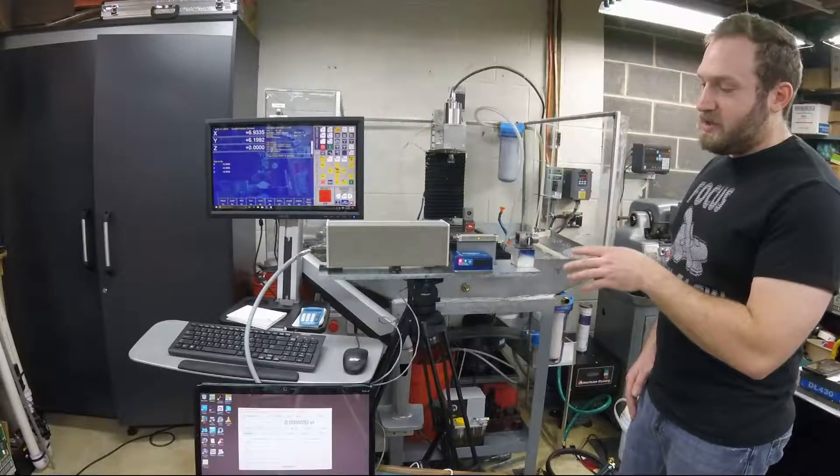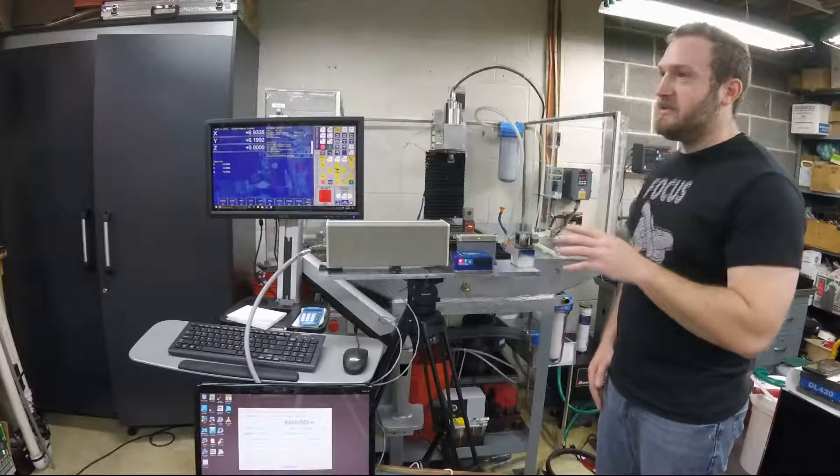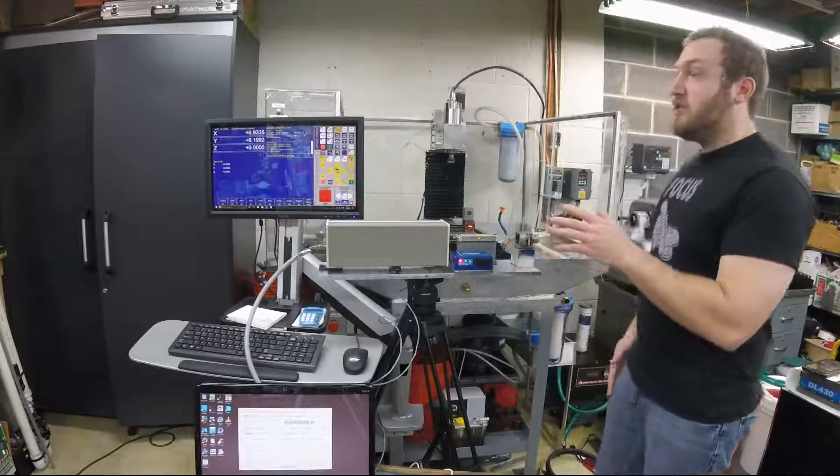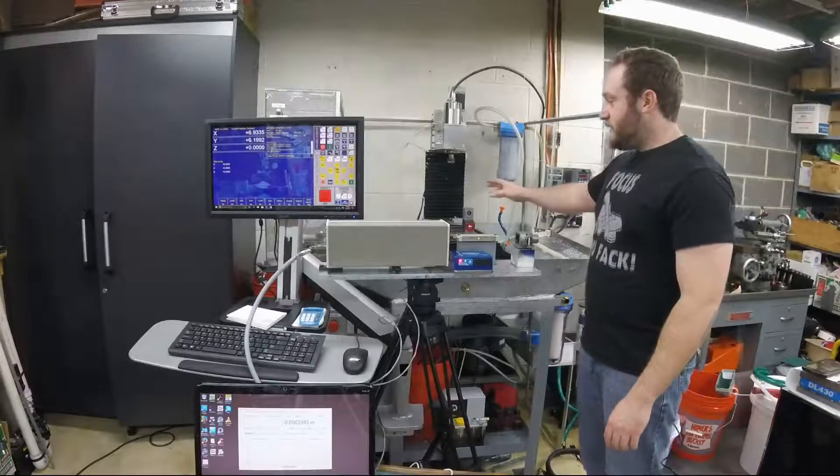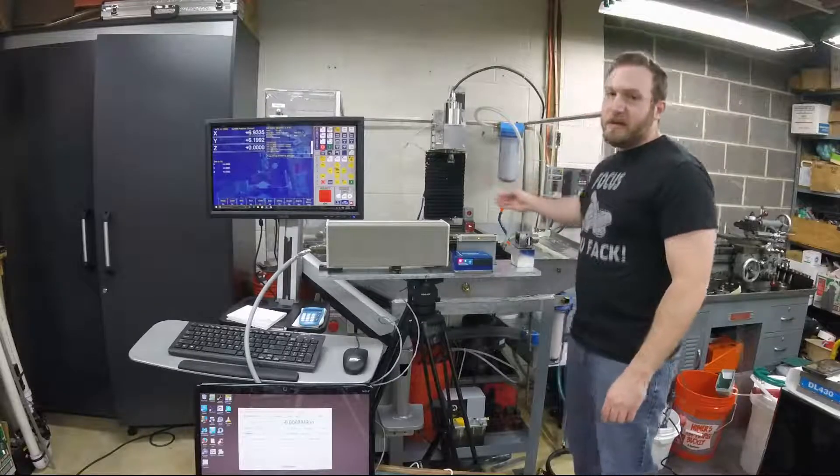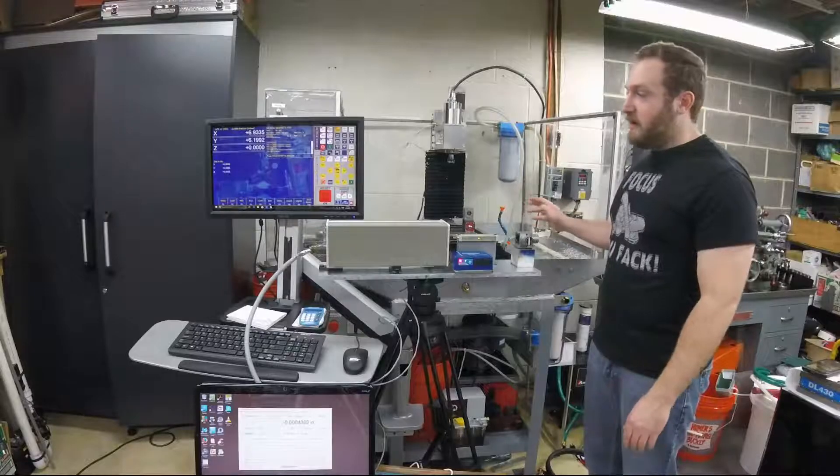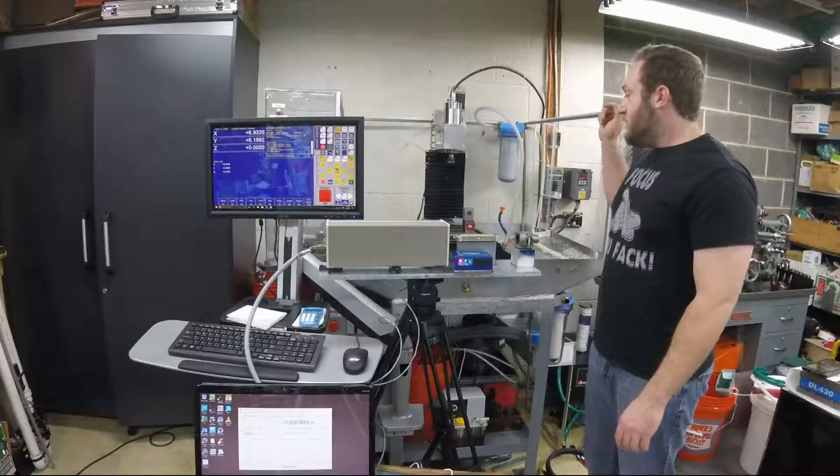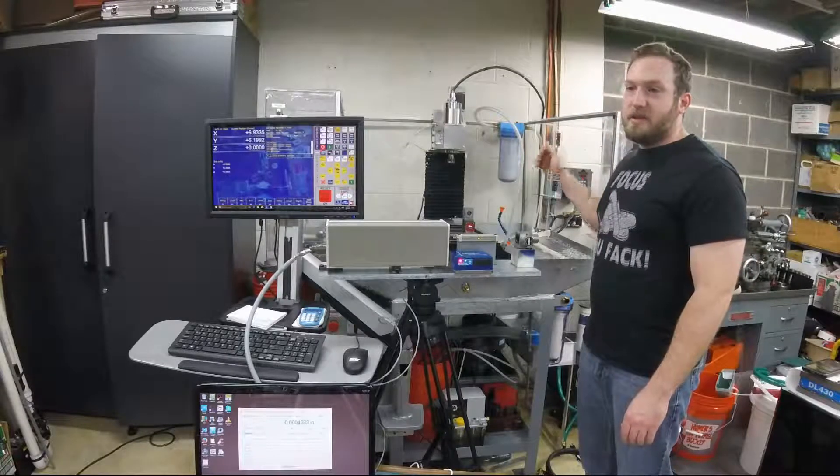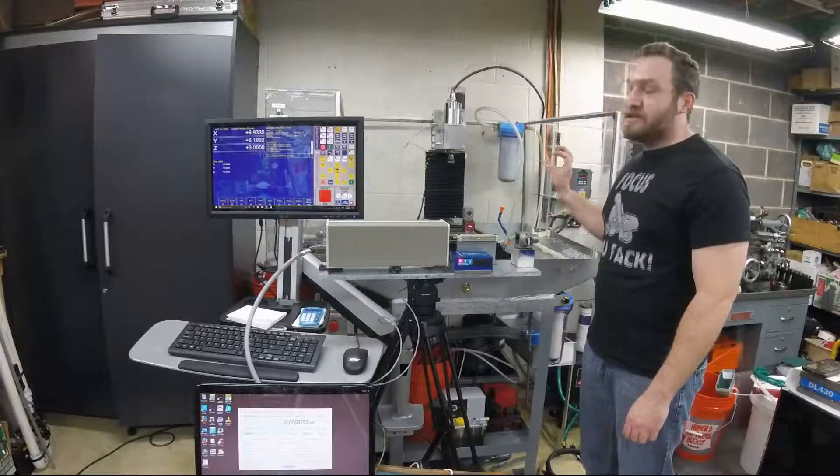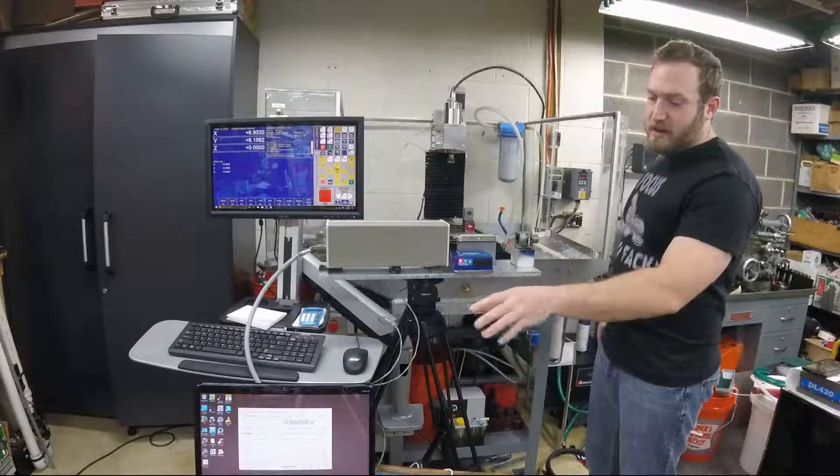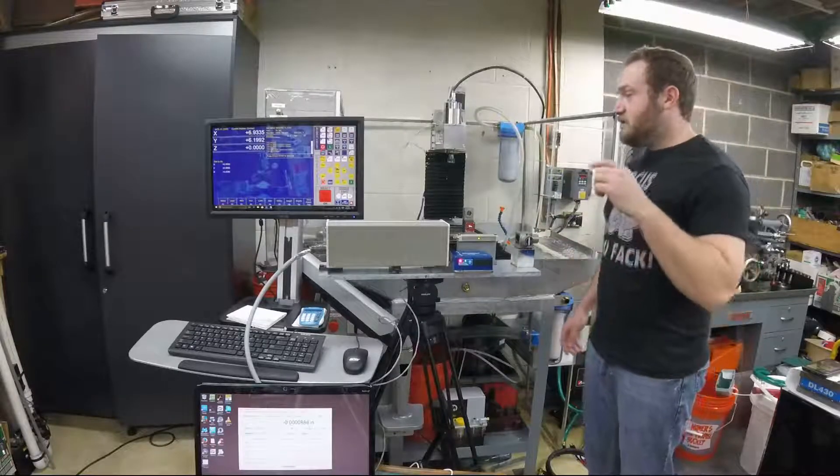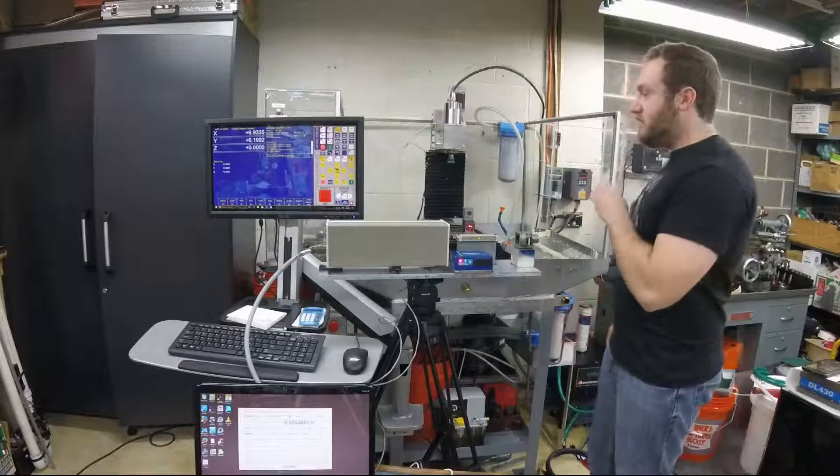But what it gives you is, you don't have to worry about being the easiest way to describe it is, square with the machine. So once you get this thing set up, which takes forever, by the way, to get the retroreflector lined up, coming back through the mirror, through the receiver, and be able to move the machine the full length, probably takes you two hours. No joke, it's hard. But what it gives you is, it gives you, by the time you've gotten that, you know you're perfectly square. Because if this six millimeter dot moves tenths on that mirror, the retroreflector doesn't see it, and it doesn't work.